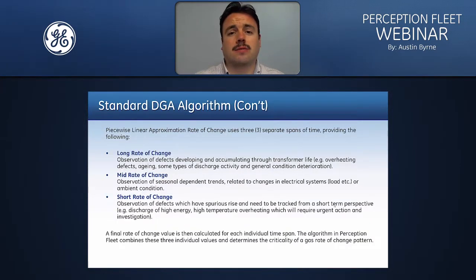Here you can see exactly what we look at in terms of what we call the piecewise linear approximation rate of change. So we look at the 3 different time spans. The long rate of change shows observations of defects developing and accumulating through the transformer's life. So that can be seen as overheating defects, aging, and sometimes discharge activity, and is generally related to the natural aging of an asset. The mid rate of change are observations that can be down to seasonal variation, where you have high levels of electrical load on an asset over a period of time, which changes over the year. Mid rate of change can also be attributed to ambient condition changes, so the natural operating of the asset in winter compared to in summer.